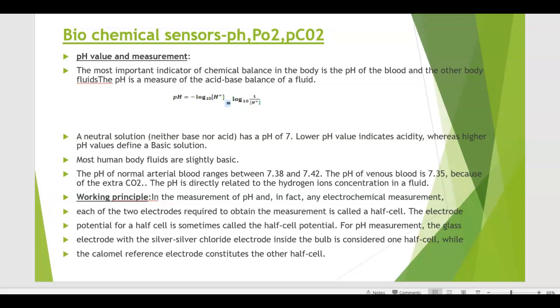Working principles. In the measurement of pH, in fact in any electrochemical measurement, each of the two electrodes required to obtain the measurement is called a half cell. The electrode potential for a half cell is sometimes called the half cell potential. For pH measurement, the glass electrode with the silver chloride electrode inside the bulb is considered as one half cell, while the calomel reference electrode constitutes the other half cell.